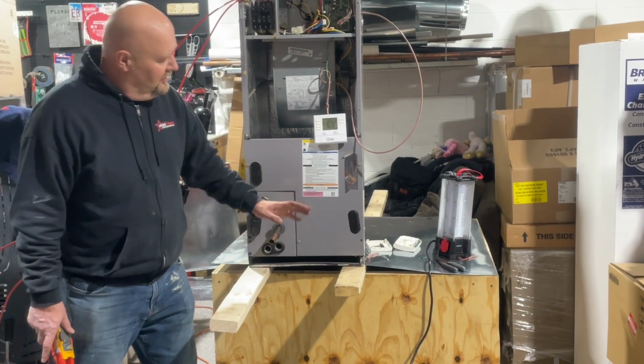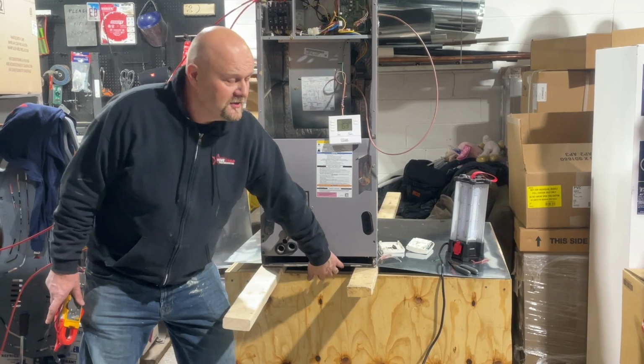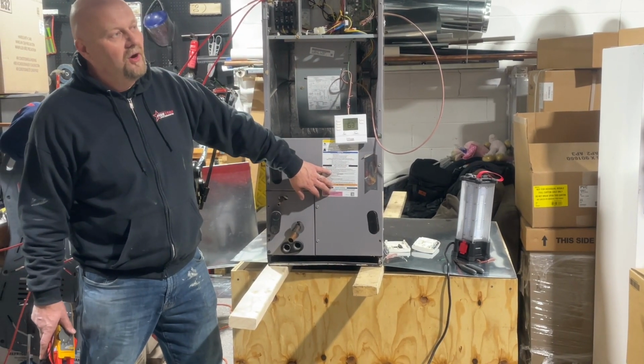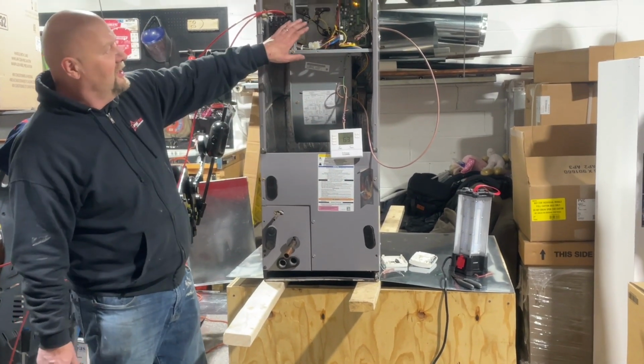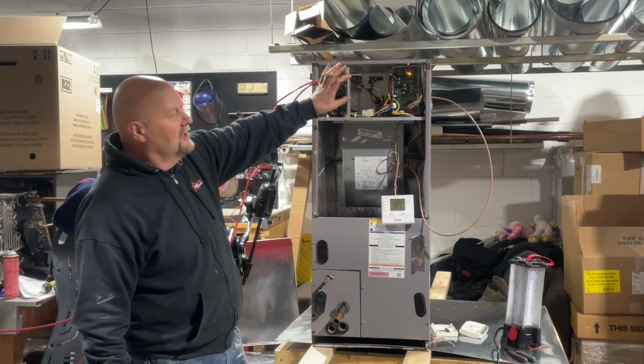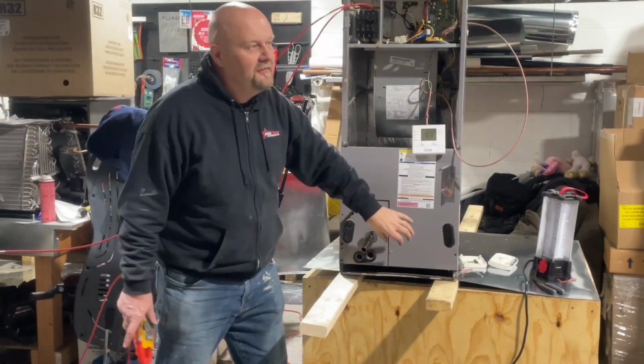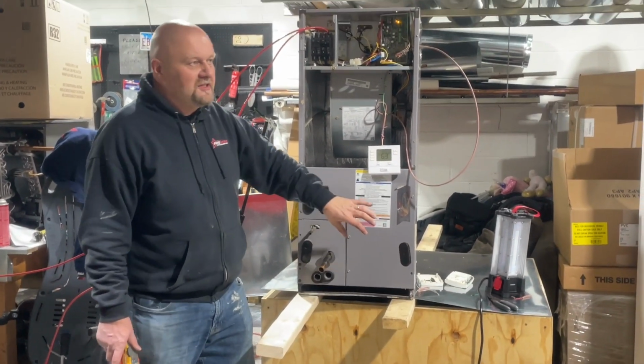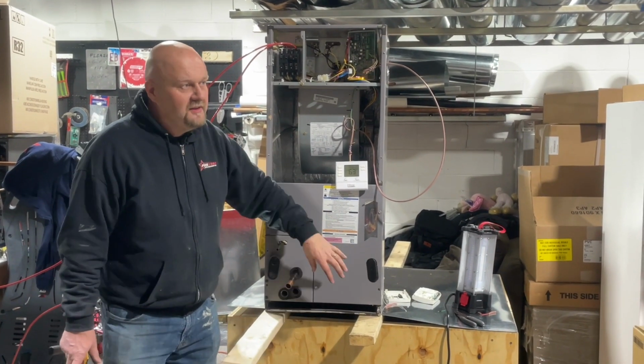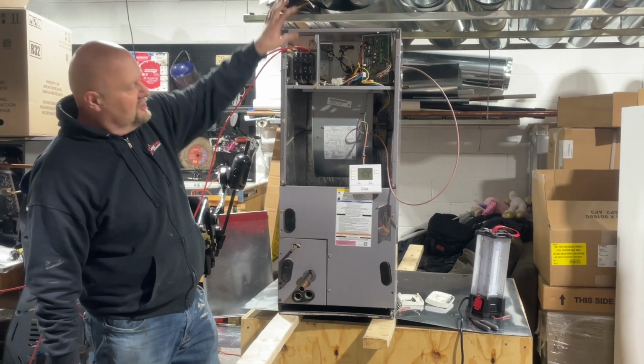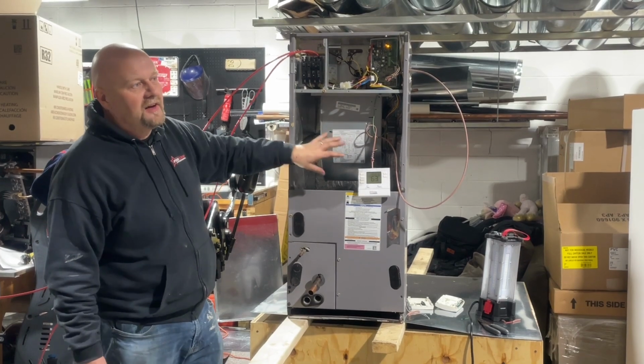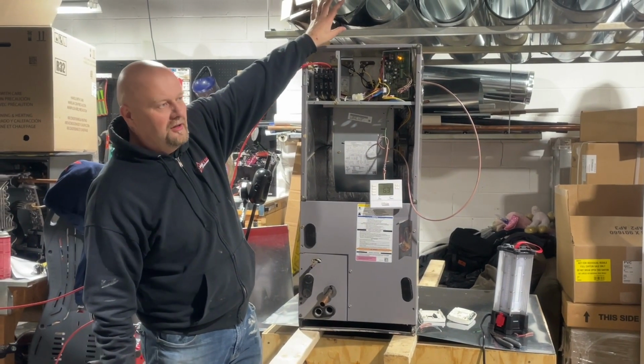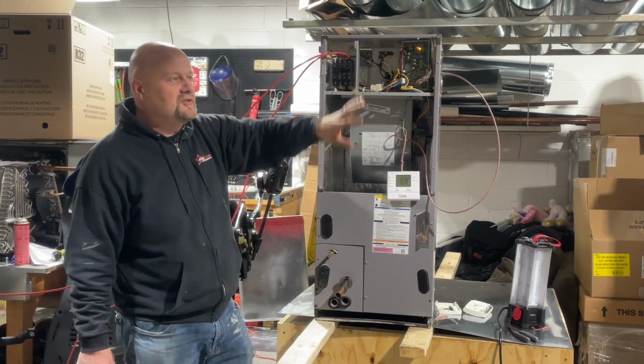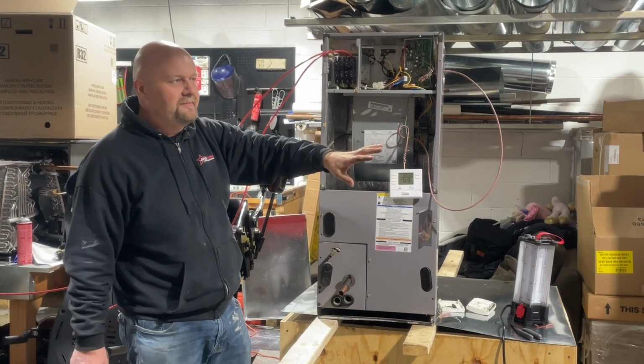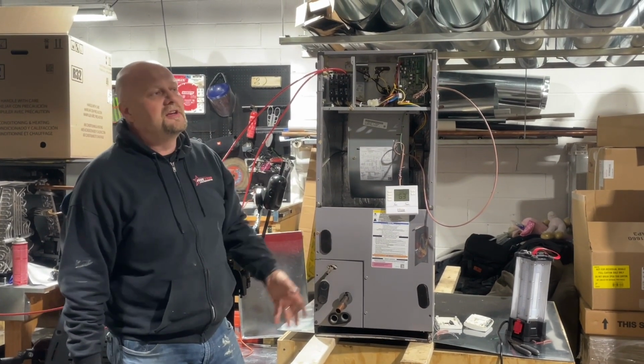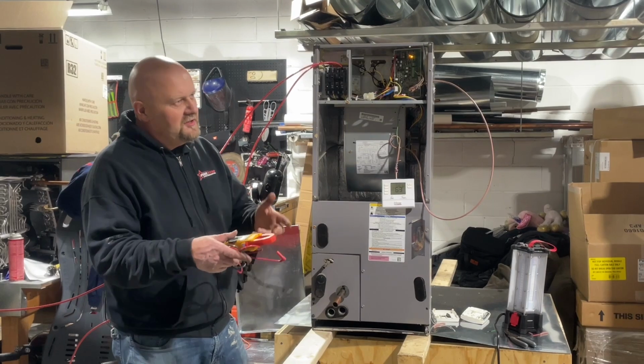Now, in here you have cool air from the house getting sucked into this coil, right? And then the electric heating part sits above it. So this part doesn't affect the coil. But if you have a standard furnace, it's reversed, right? The coil sits on top of the furnace. So then the heat from the gas-fired furnace will be affecting the coil, right? And we don't want that because the refrigerant going through is already hot, and we cannot take superheating it even more. Do you understand now? Yeah, makes more sense.